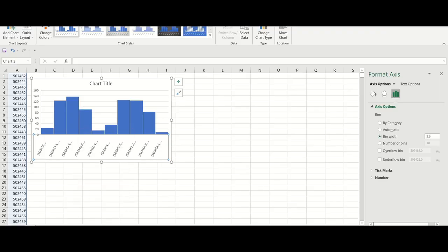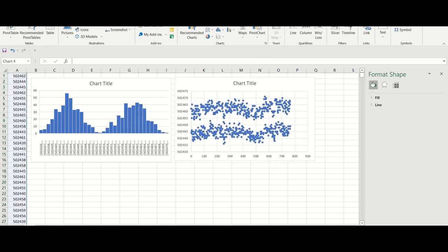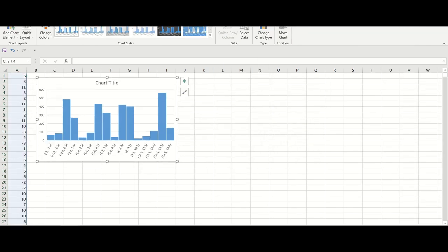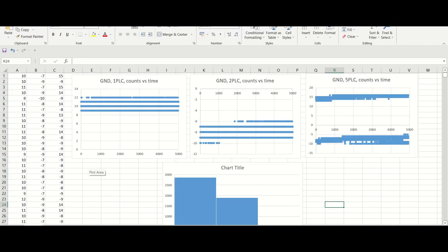Logging and analyzing the results showed that not only is the thing noisy, but it can't seem to decide on what digital code to output for the same input voltage. This trend got worse over more integration cycles, with the readings diverging into 4 groups. I ran some more tests over various PLCs and noticed that the divergence happens at around 5 PLC.